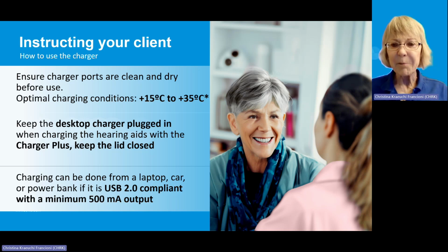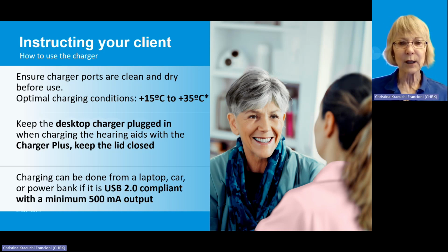Second, for optimal charging, be mindful of the temperature because all lithium-ion batteries are sensitive to temperature. Don't store your hearing aids and charger in a very cold or very warm location, such as windowsills, under direct sunlight, or too close to a radiator. The optimal charging temperature for Sonic A1 instruments with contact charging is plus 15 to plus 35 degrees Celsius. And for Radiant and Captivate with inductive charging, the optimal temperature is plus 10 to plus 35 degrees Celsius.